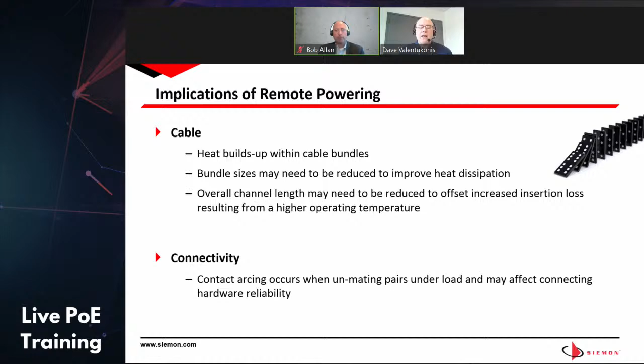When you deliver power, obviously you're adding heat, and there's a manageable number of implications that we'll talk about today to make sure you're properly prepared, and then figure out some ideas on how you can address them during the installation of this low voltage cabling. The primary thing we're going to deal with is the heat buildup within the cabling as you add power to the communications. But we can manage the length and reduce bundle size, and we'll talk about that. And then there's the connectivity element when you're disconnecting from a powered connection, and how you can address that. We'll walk through that as well.